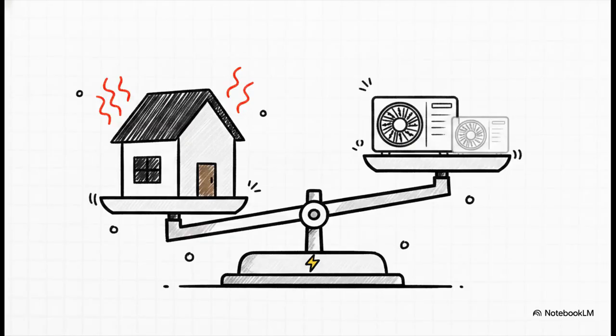This is incredibly important. Do not let a contractor convince you that buying a fancy, high-efficiency SEER 2 18 or 20 unit means you need a bigger tonnage. The actual physical heat load of your house hasn't changed just because the new machine uses energy better. The sizing logic stays exactly the same no matter how high that SEER 2 rating climbs.